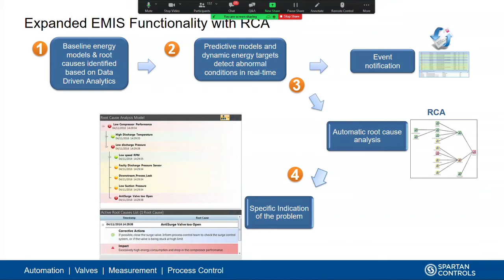So now instead of waiting for that 1 month in that example that we showed where we had a motor fault, we would have seen that we had a motor fault right away. We'd probably even see we had a motor fault before it started causing high energy consumption. But if we didn't fix it and it did start to lead to high energy consumption, we would have flagged that very quickly and then been able to organize the repair of that motor and save 1 month of high energy consumption. So if you start taking a look at those events, you can very quickly justify the effort that it takes to stand these systems up.